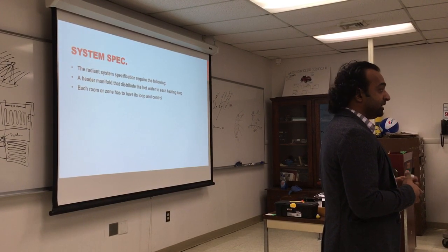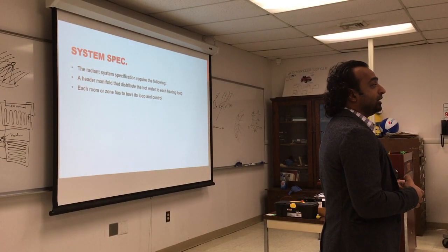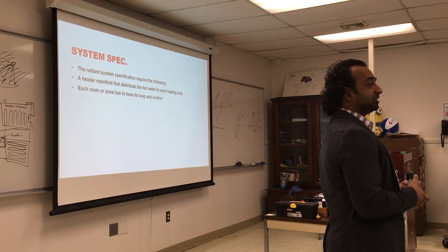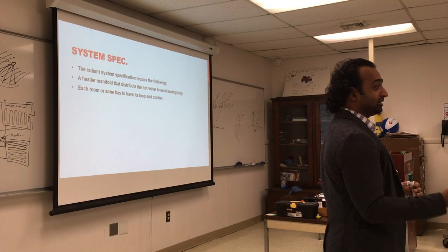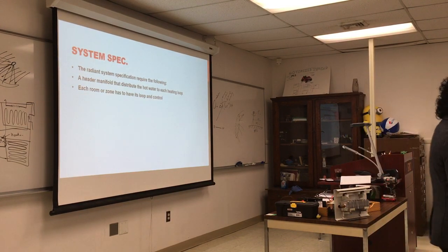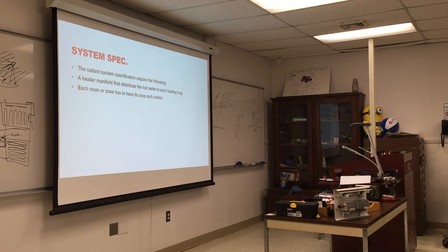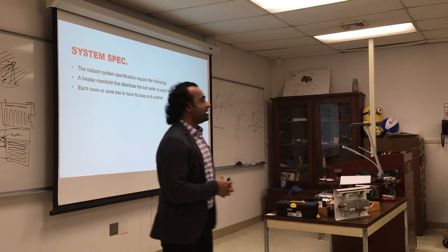I've seen people doing PEX tubes for that. I personally feel PEX tubes are good, but they have not been in the field for a long time. Meanwhile, we have copper tubing that's been there for 40 years. I'll trust something that's been there for 40 years. PEX tubes have been found to sag after a while, they deteriorate, and the connections get loose. So again, that's something you have to think about, and it comes with experience.